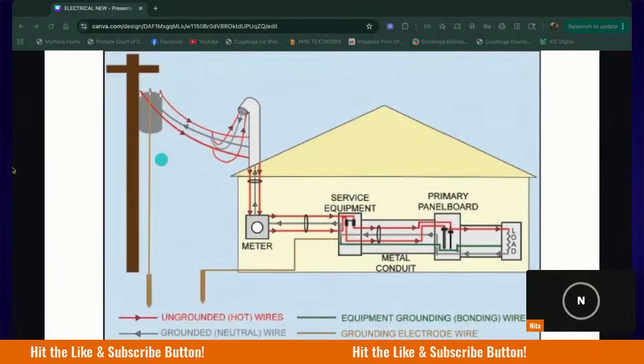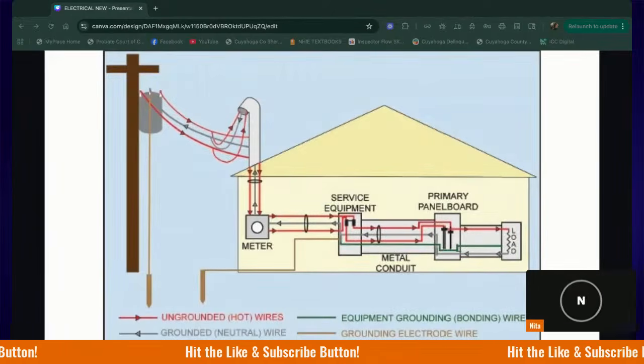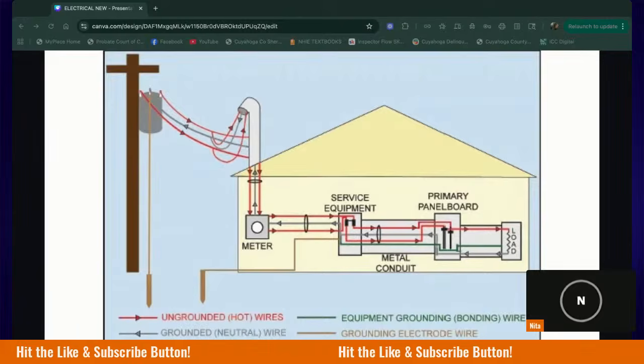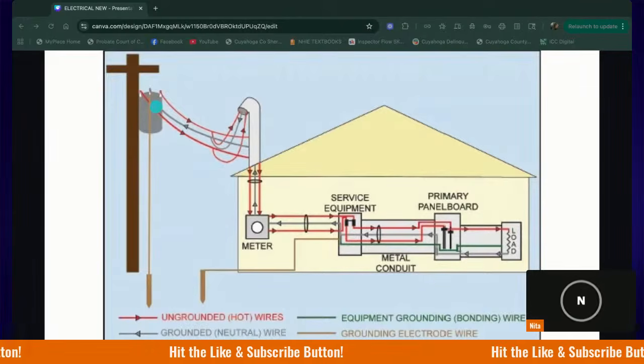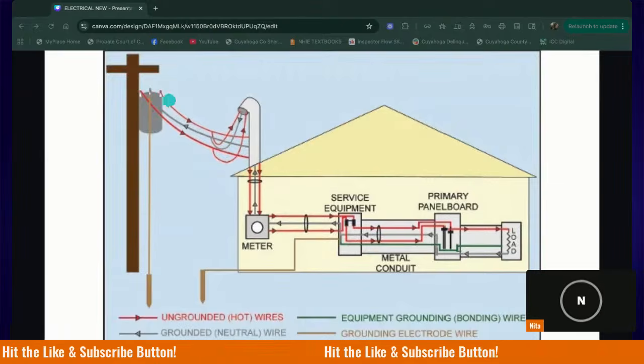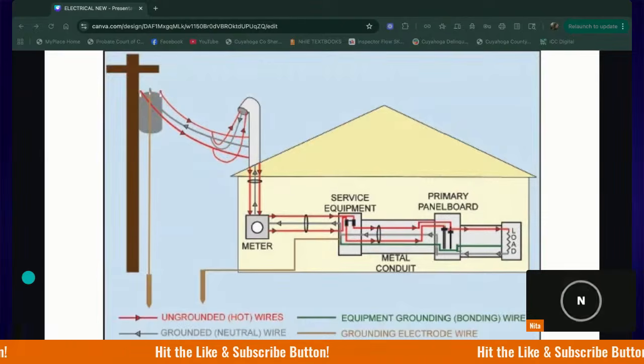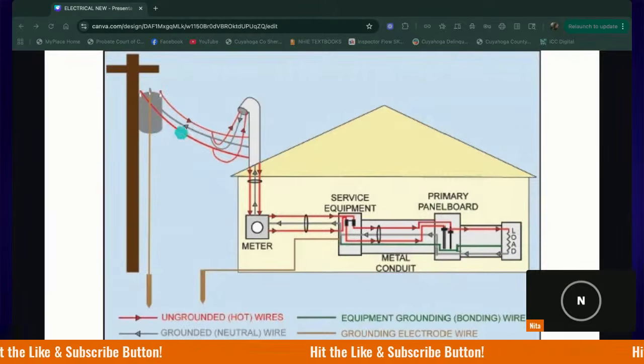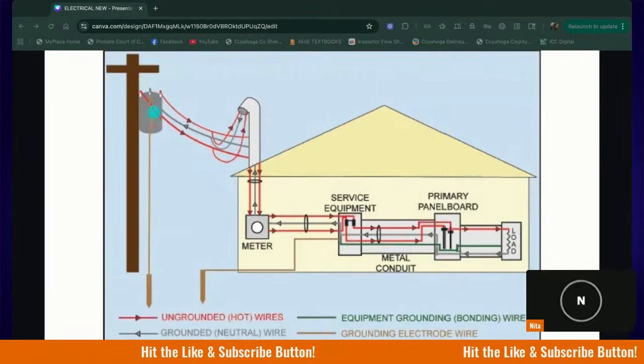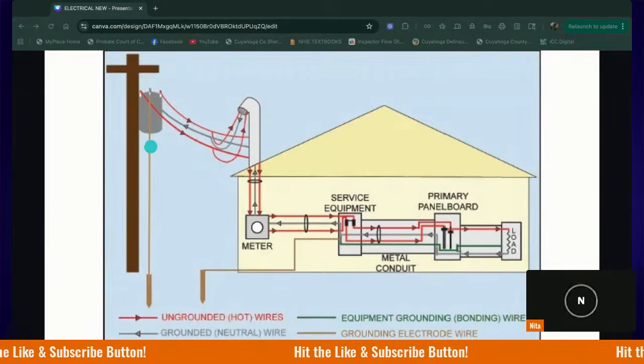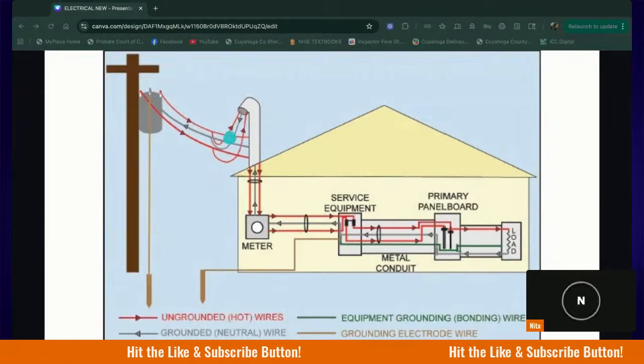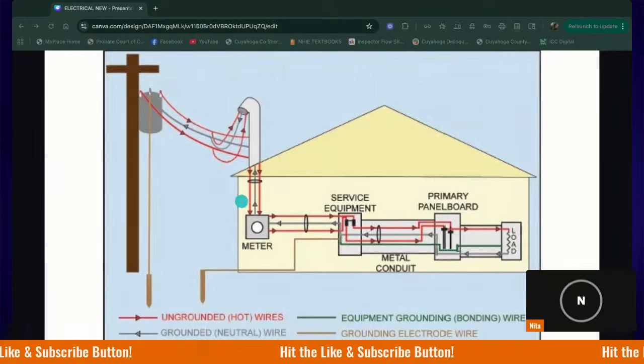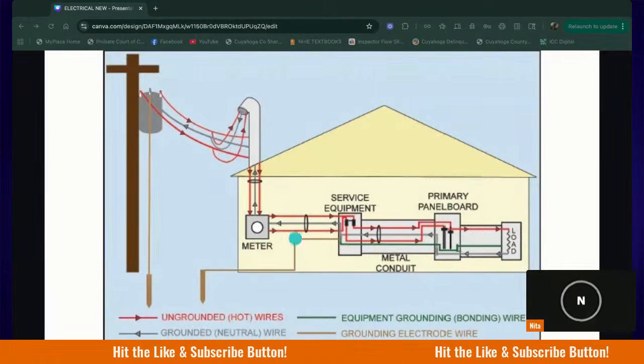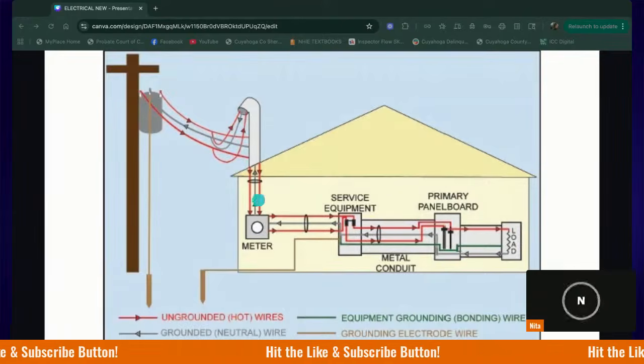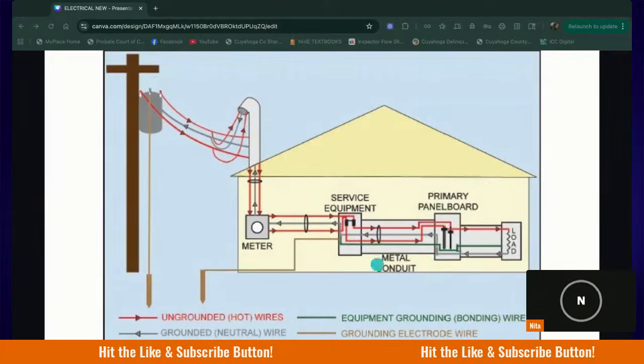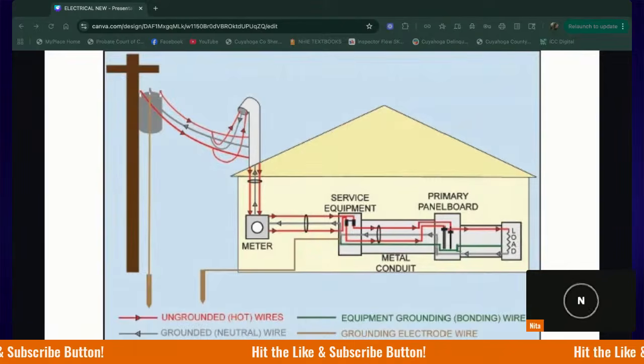Okay, so now we're looking here. So again, in this diagram, we have our two hot wires coming from our transformer. And then we have our neutral wire or our grounded conductor is in gray. Coming service drop, service point, service entrance conductors, drip loop, through the weatherhead, down the mast, meter base, panel. Okay? So boom, we're right here now with the service equipment.